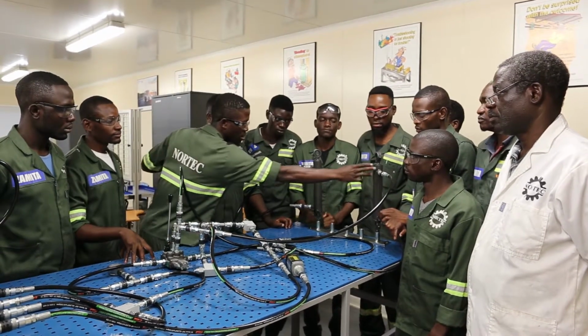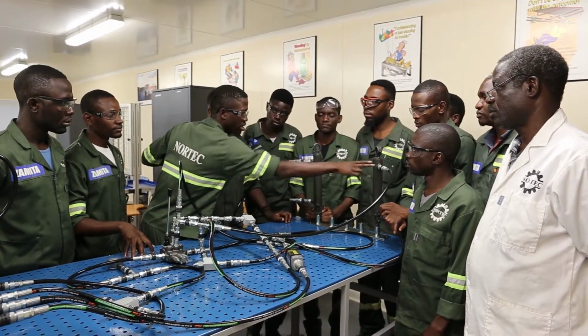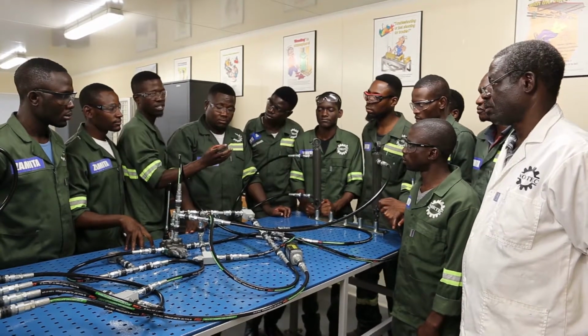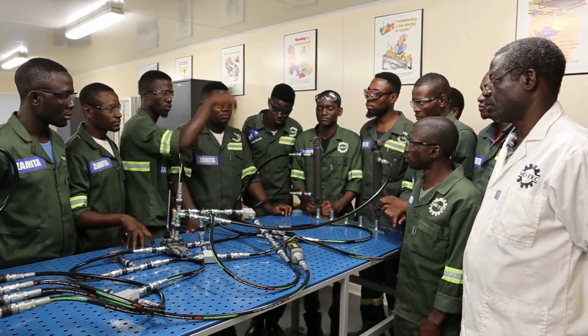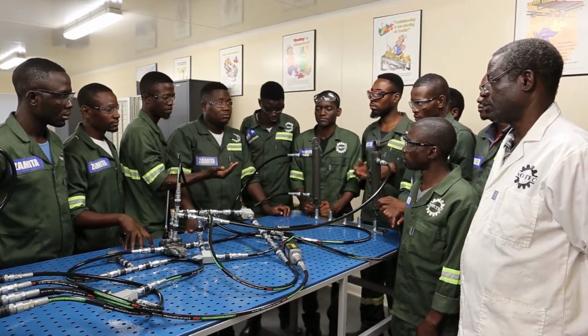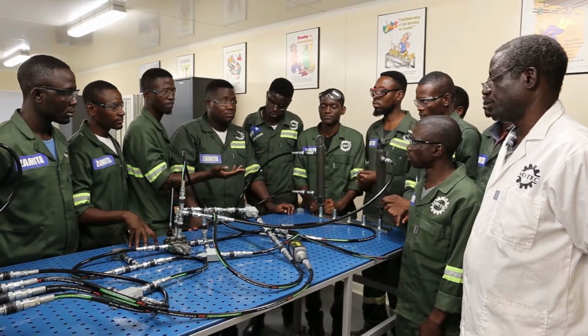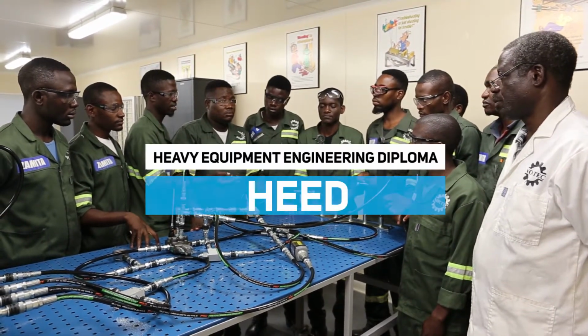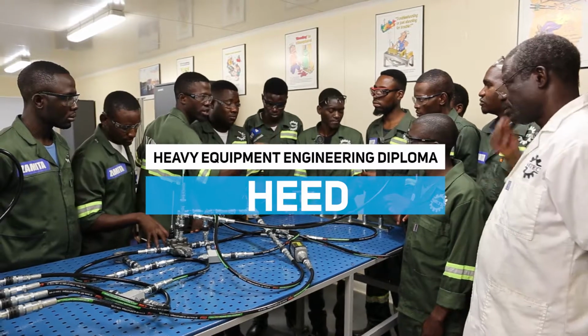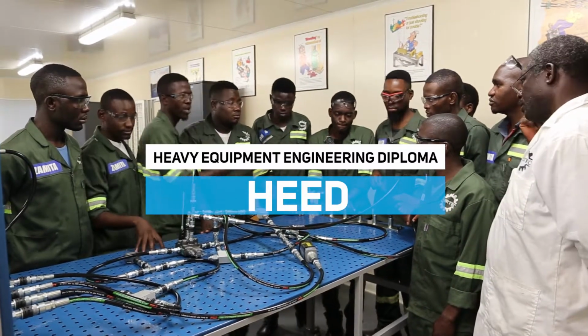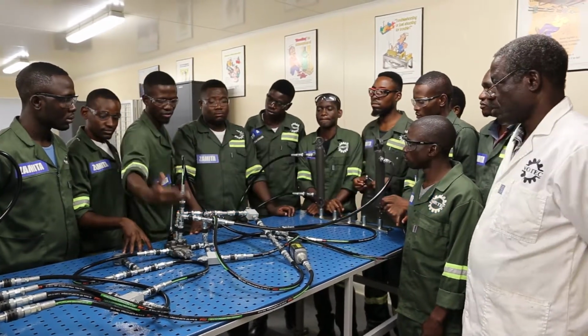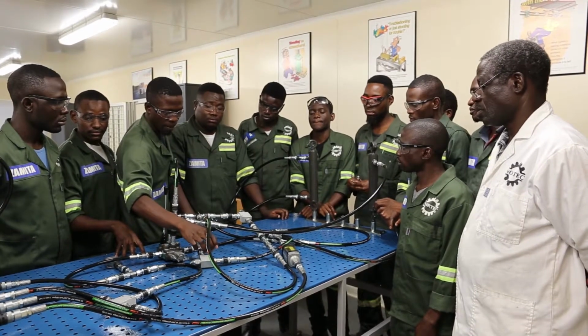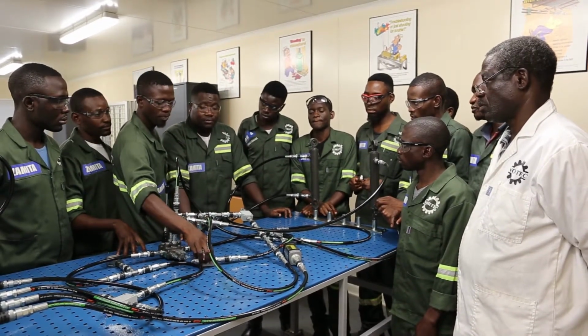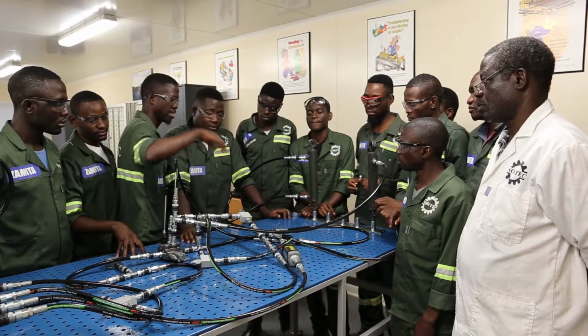This one is our primary retracting cylinder, and we know that we have a difference in surface areas at the rod side and at the base. So yes sir, meaning we need more pressure to retract than to extend. That is why we had to differentiate the pressures between the retracting relief valve and the extending relief valve.